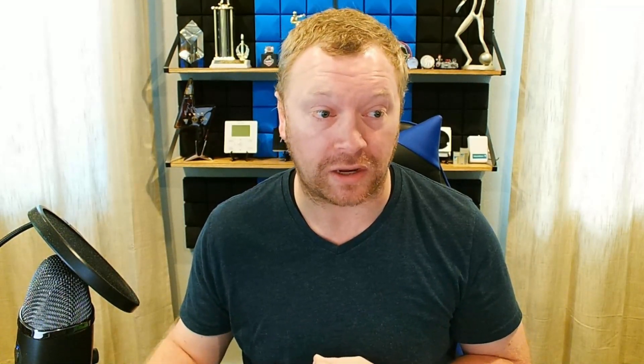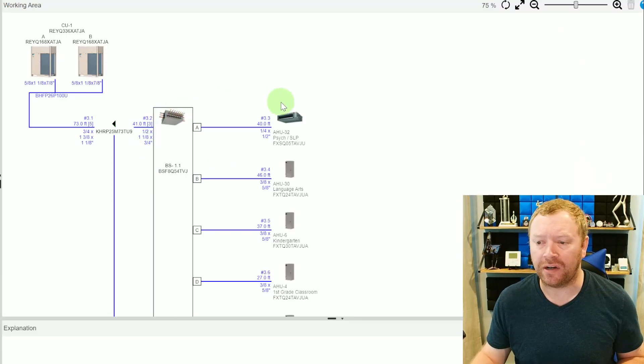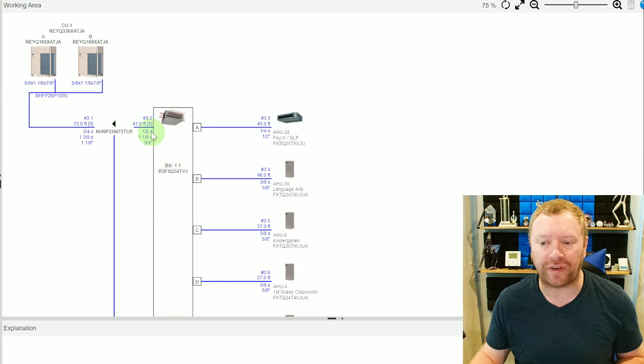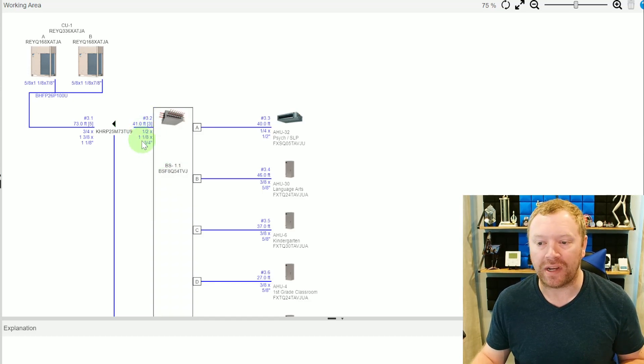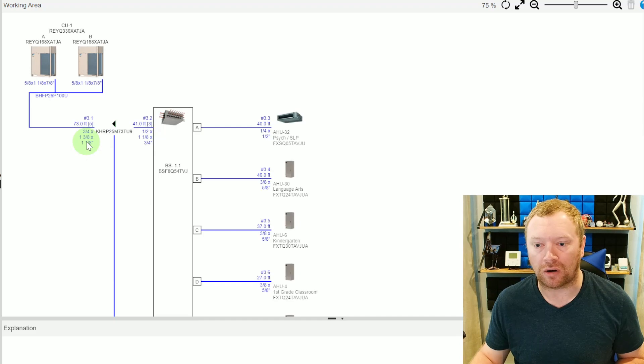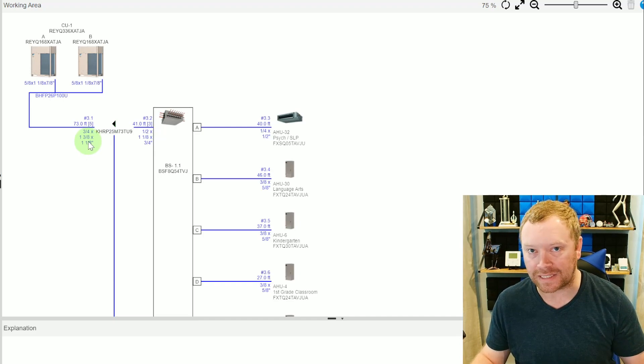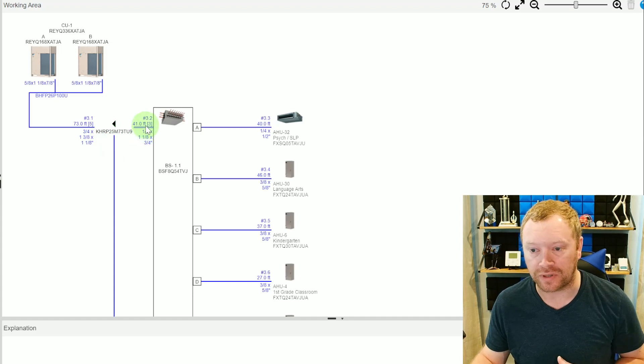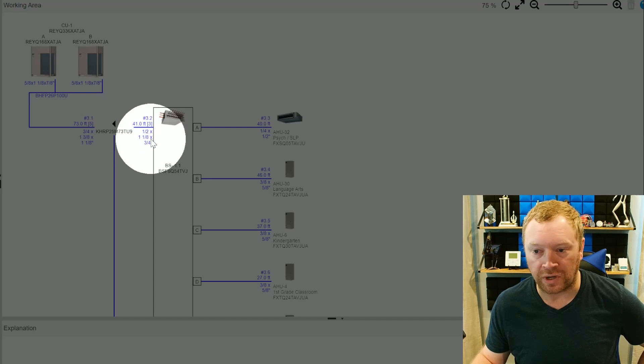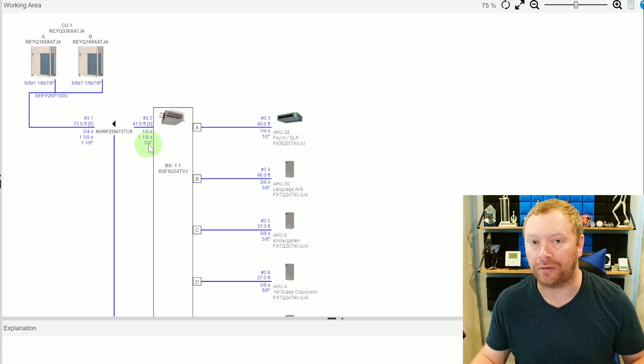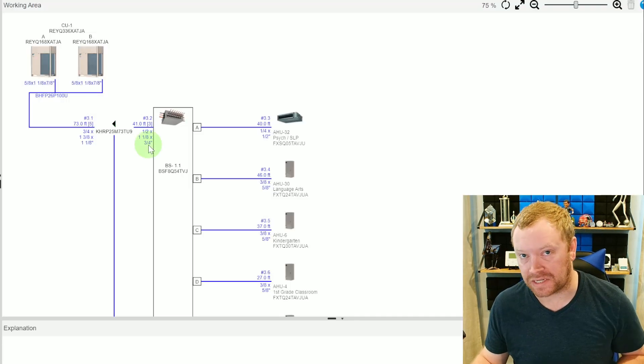Maybe there's a beam that we have to go under or over or around, or we can't do a straight point-to-point line set run to get into a classroom or an office. Maybe we need to go around the hallway. It is their job to take that piping schematic that is printed out so that they can see all the lengths of all of the runs within the system, and they're supposed to go through the floor plan on site and confirm if there needs to be any immediate changes. If there are, we go back to our software, we update that. Because what we want to make sure is that none of these lengths are going to affect these main pipe sizes.